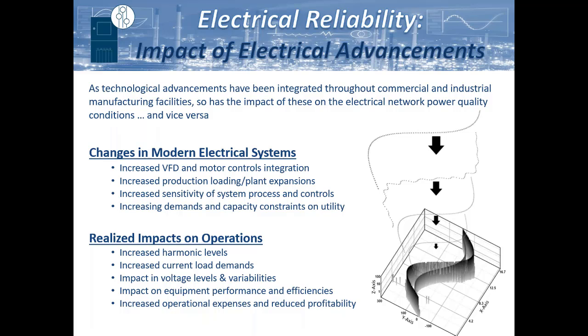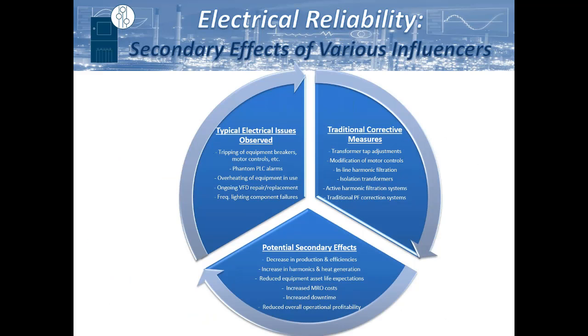And once improved upon, the secondary impacts, which are oftentimes lagging indicators, are quite significant. And being able to analyze those after the fact, and the impacts that they're having, can have a dramatic impact on an operation, their efficiencies, and their profitability. So some of the traditional electrical issues that are often observed out in the field are nuisance tripping, whether that be of breakers or motor controls, VFDs, phantom PLC alarms, or that may impede on a process.